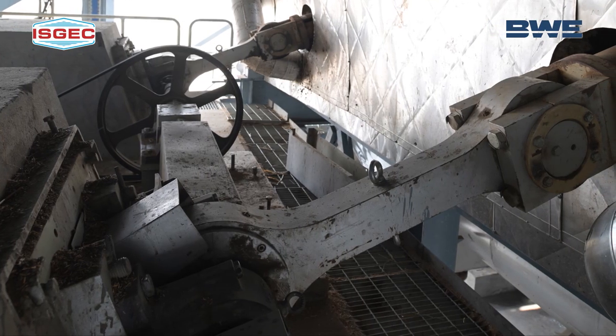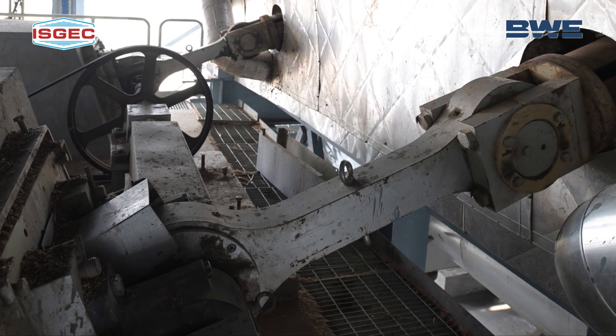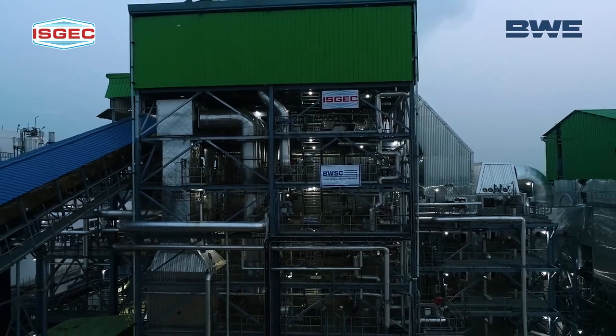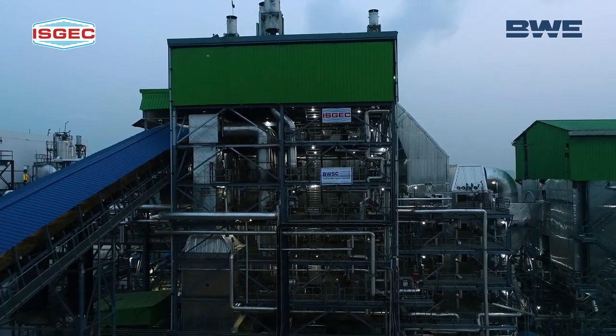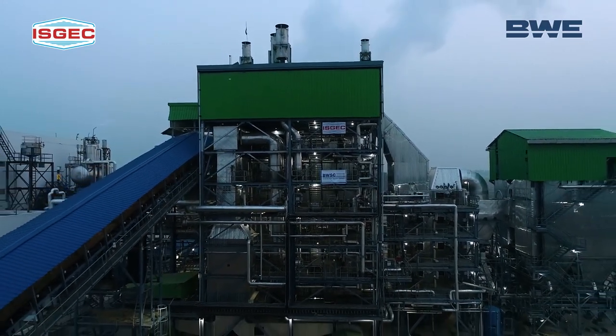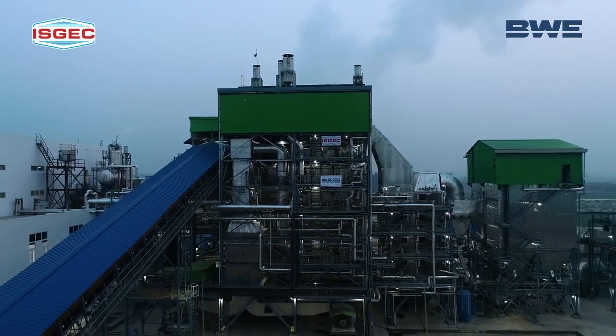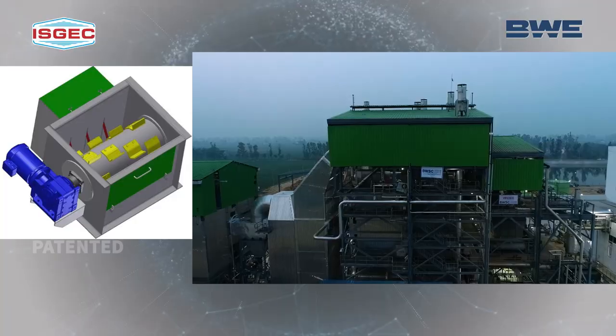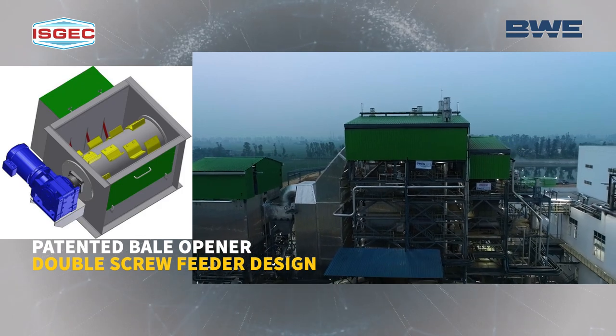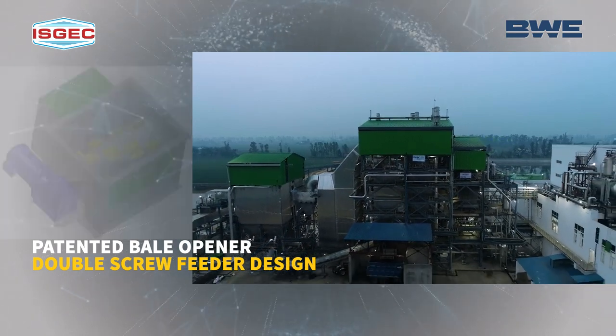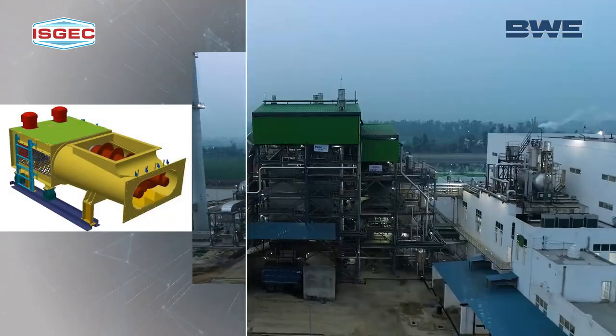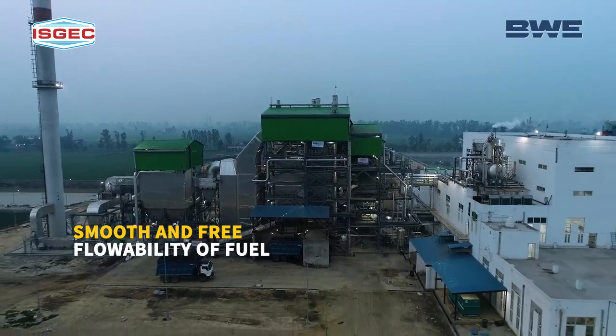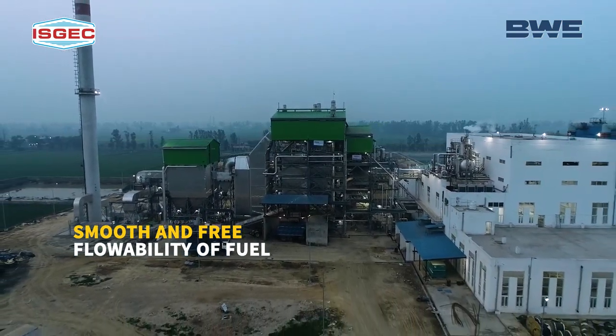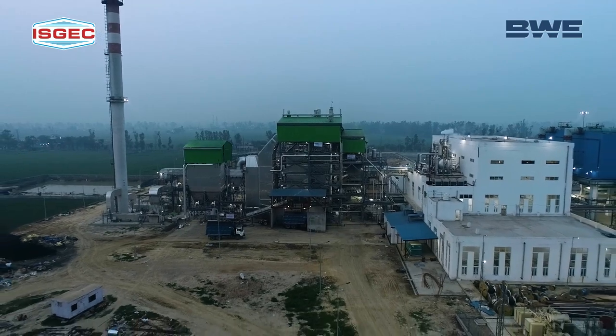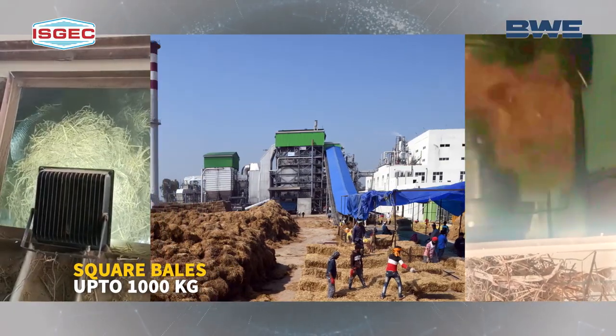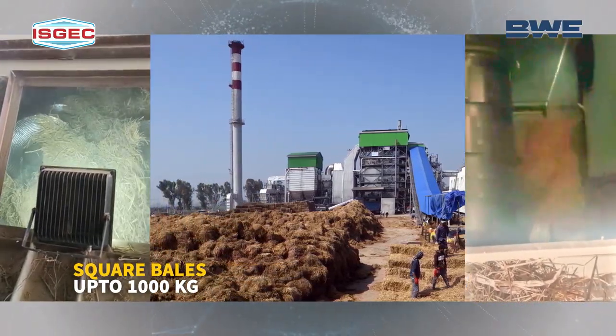The specially designed grate drives provide turbulence to the fuel, ensuring efficient burning and a drastic reduction in the percentage of unburned fuel in the bed ash. The patented bale opener and conservatively designed double screw feeder design ensure a smooth and free flow of fuel to the furnace. The boiler is designed to take square bales of up to 1000 kilogram weight.